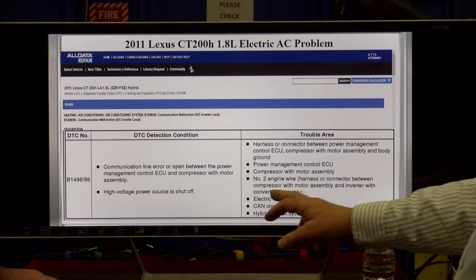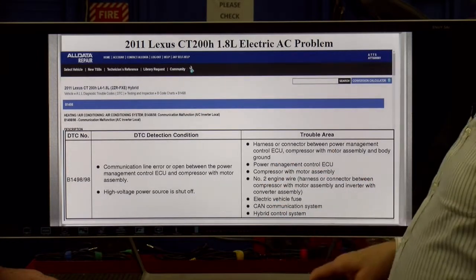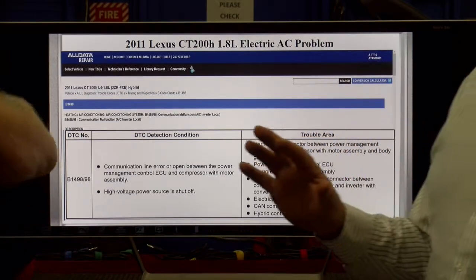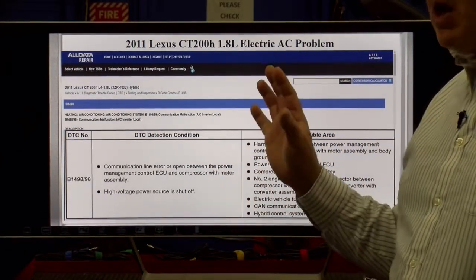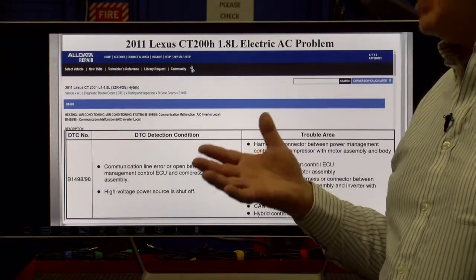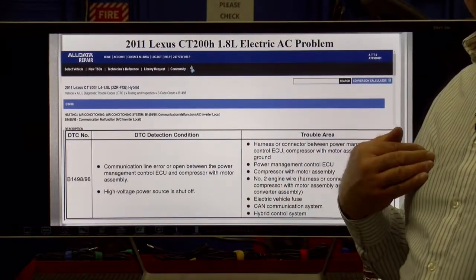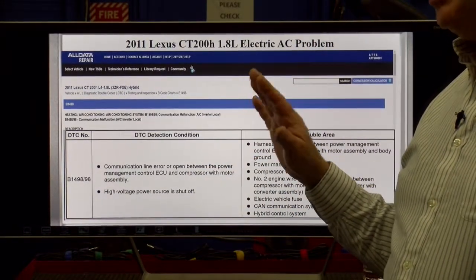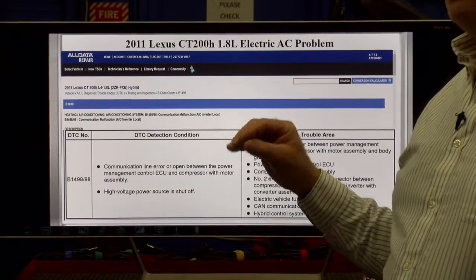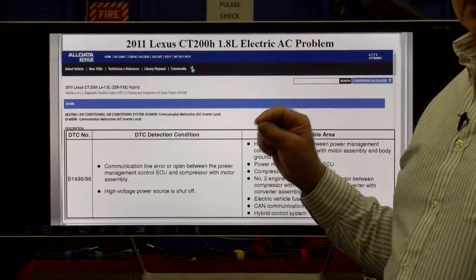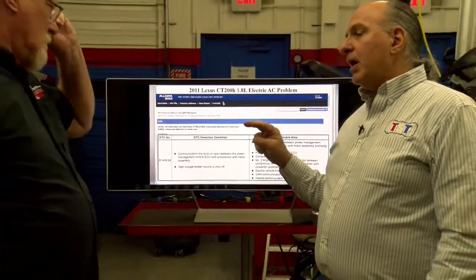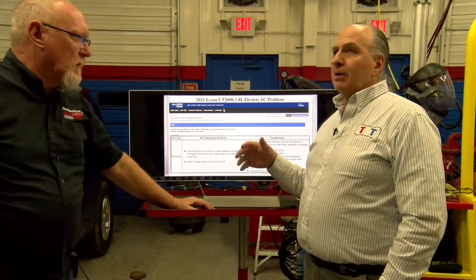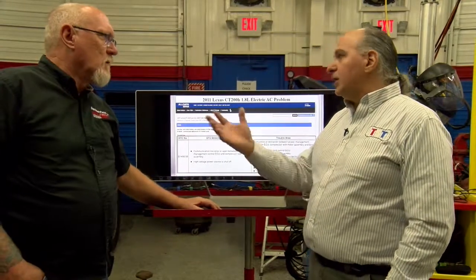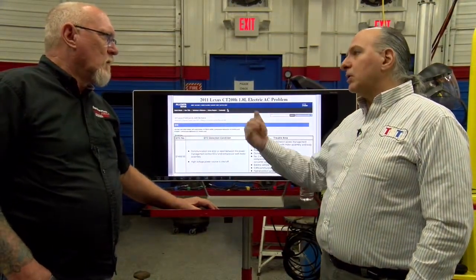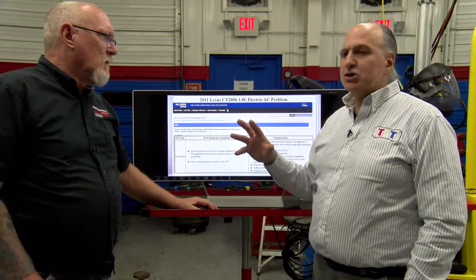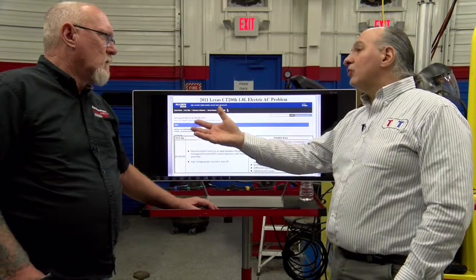Wire and harness or connector between a compressor motor assembly and inverter. Well, from what we can see, now I'm not saying that this wire doesn't have an open in it. It's a possibility, but we did not have time to check that out. So what we would do with that is we would shut the main power off, make sure the capacitors are drained down in the inverter, open the inverter up, use our meg ohm meter, go on that circuit, and read factory information, because it may tell you put 500 volts, put 250 volts. Years ago, you used to say whatever power going through, you double the power, but Toyota has specific recommendations. So we would look at that. I would think roughly they're going to say about 250.